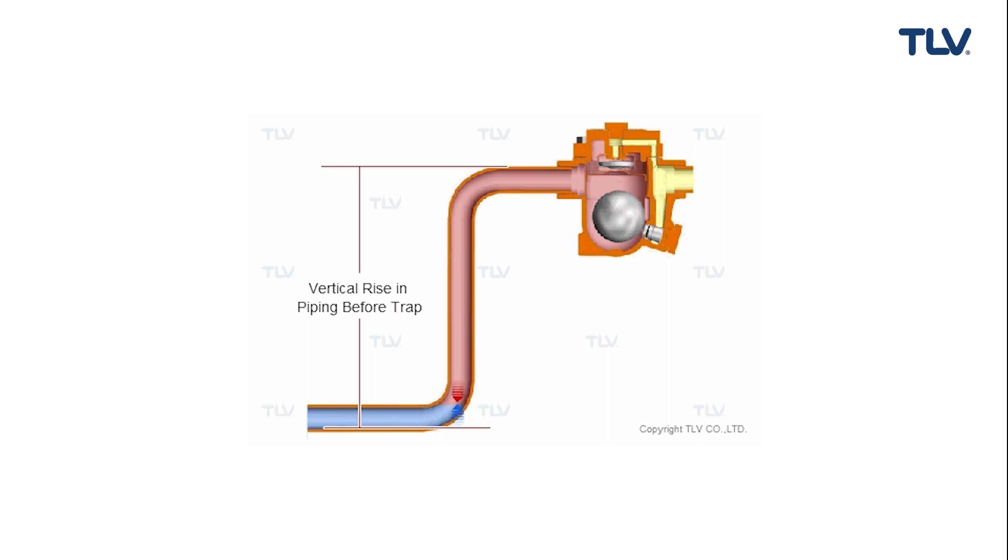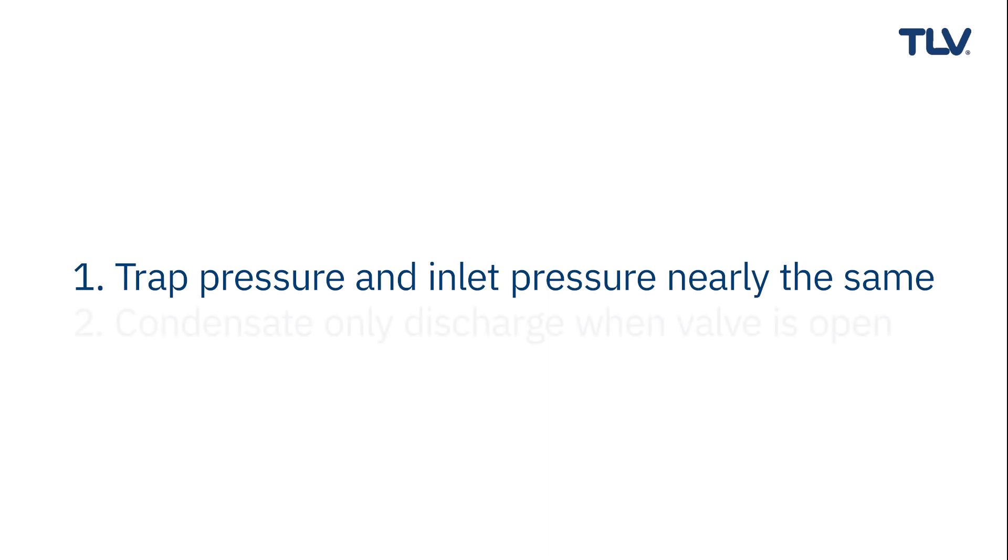You might not expect steam locking to occur if the hydraulic head pressure is large enough to overcome the steam locking. However, head pressure cannot resolve this type of problem because of two following points: the pressure within a trap and within inlet piping leading to the trap are virtually the same, or condensate is discharged only when the valve is open.